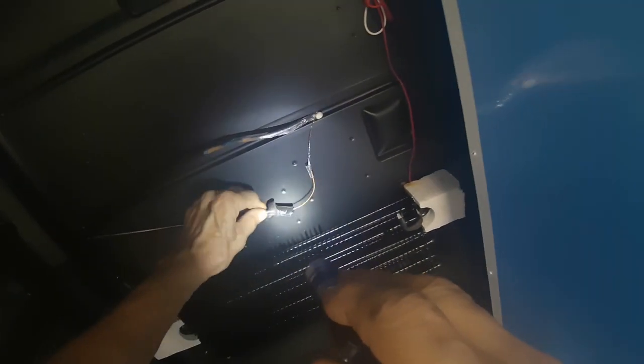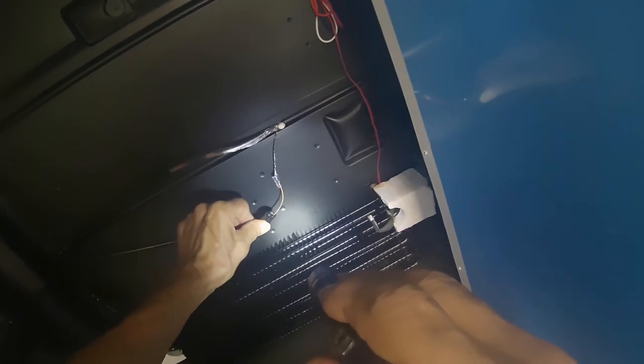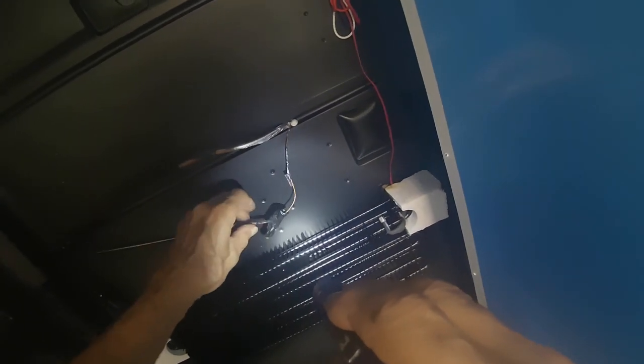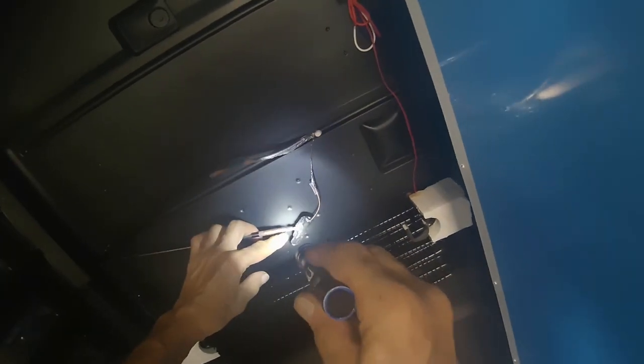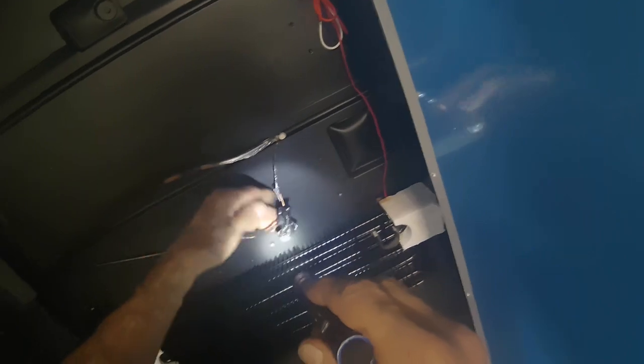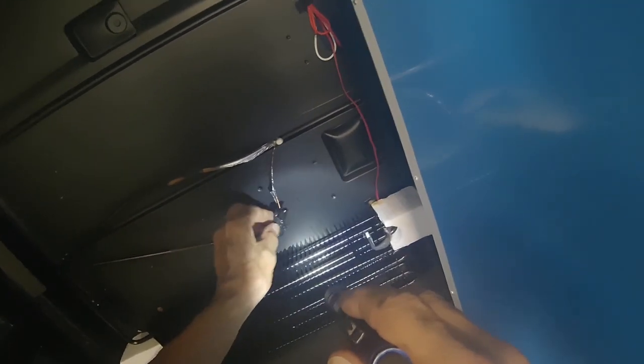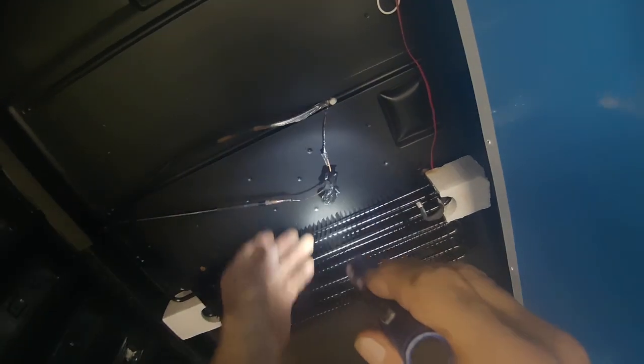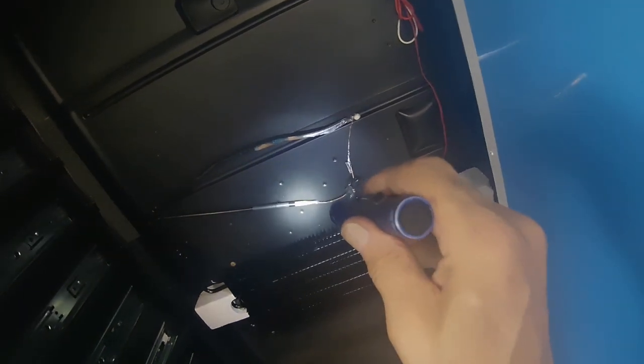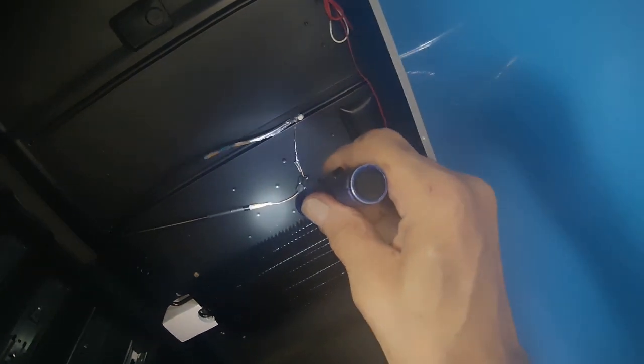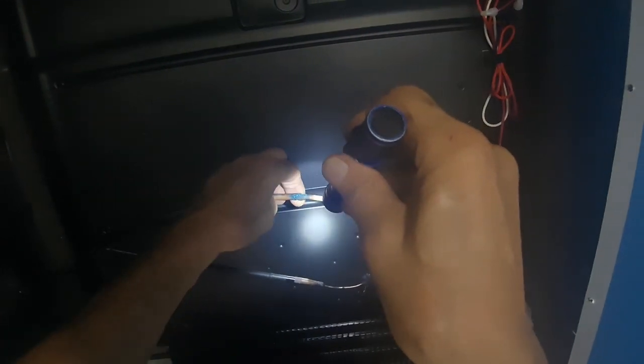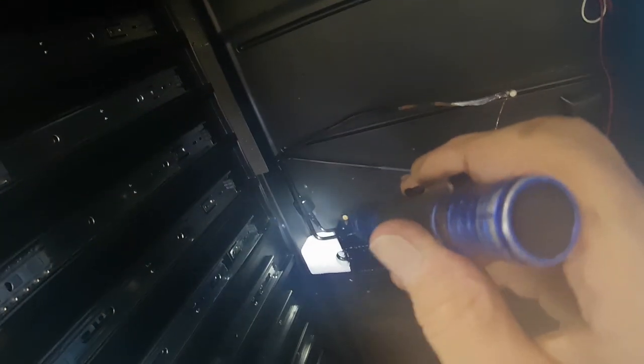And we need to find out where. If it's restricted, it would be plugged up, so we could unsweat this capillary tube here. All right, you can unsweat it. Don't know how we're going to do that, because if there's refrigerant in there and it's R600, that's flammable. I do see a little oxidation here. So, you know what we'll do? Let's pressurize it with nitrogen and see if we can pick anything up.